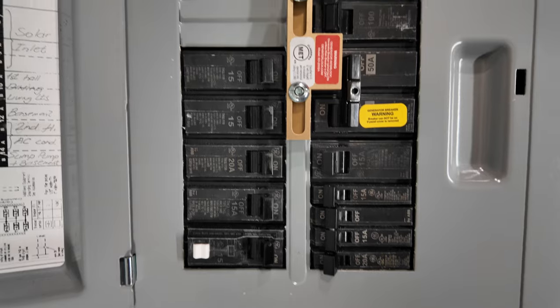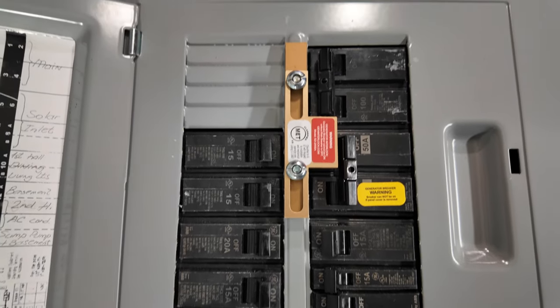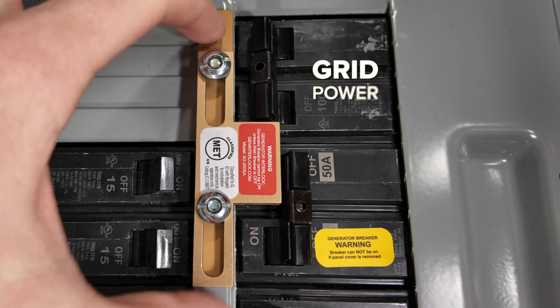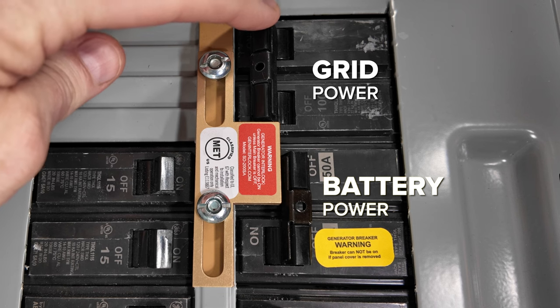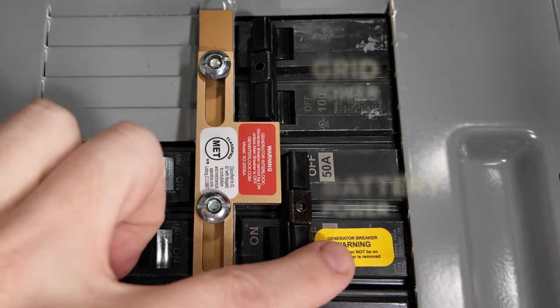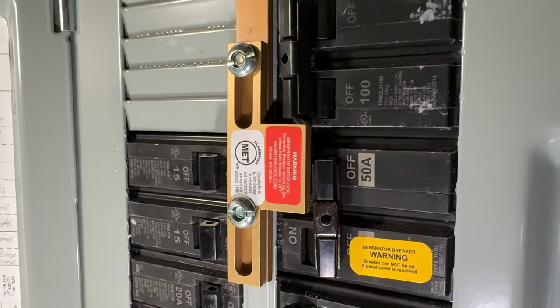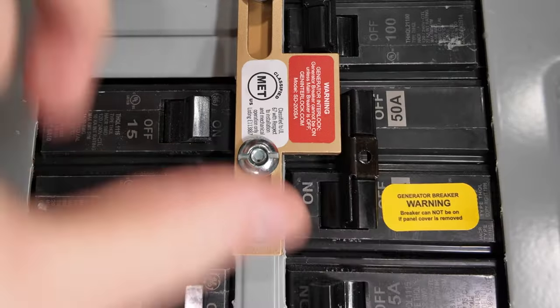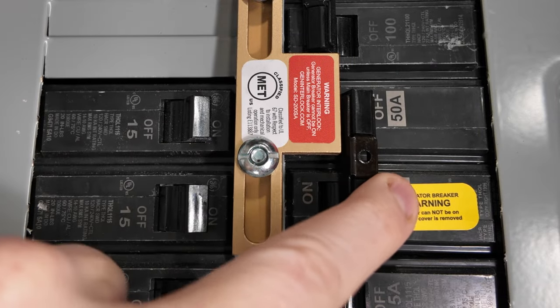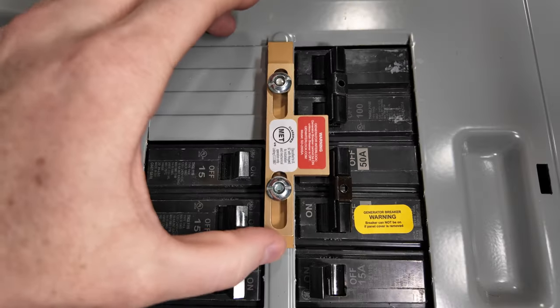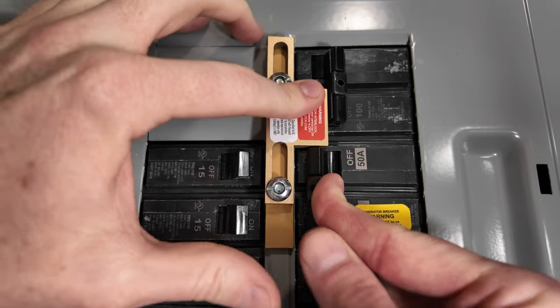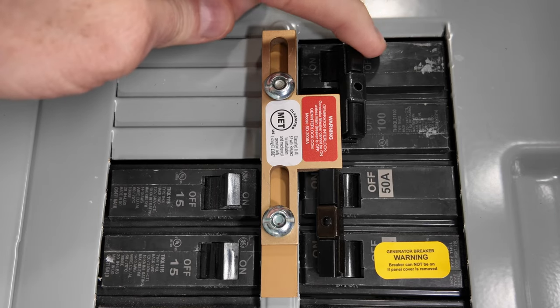An interlock is relatively inexpensive because it's just a simple piece of metal that prevents you from turning the grid and battery breakers on at the same time. When one is on, the other is locked out, and vice versa. For example, when connected to the grid, this metal plate makes it impossible to flip the breakers on from the power station, but if you flip the grid breakers off, this piece can slide down and allows the power station breakers to be flipped on. That's all there is to it.